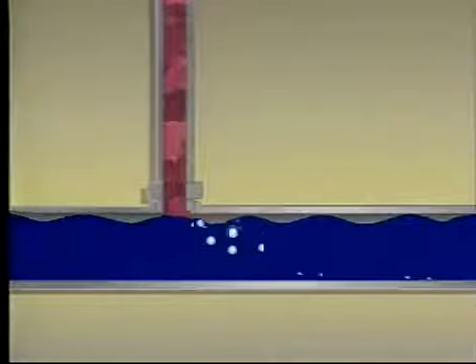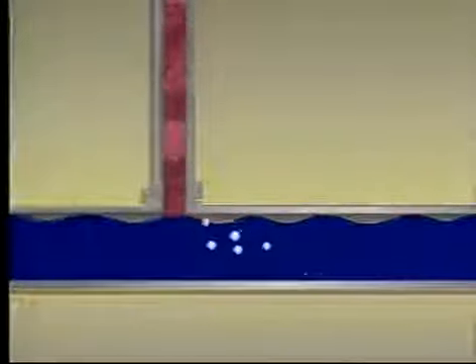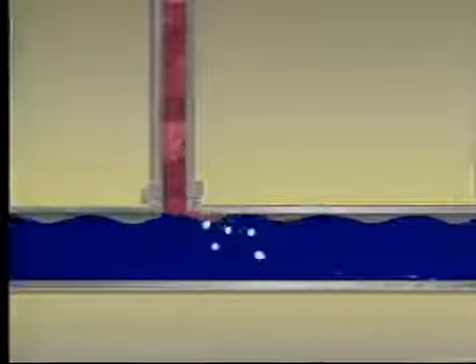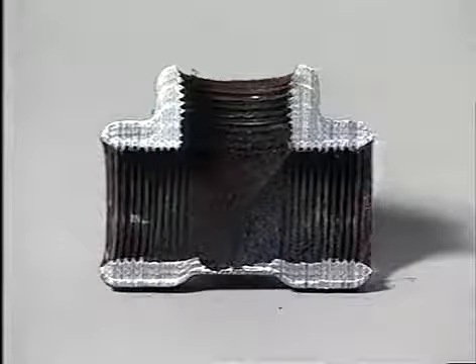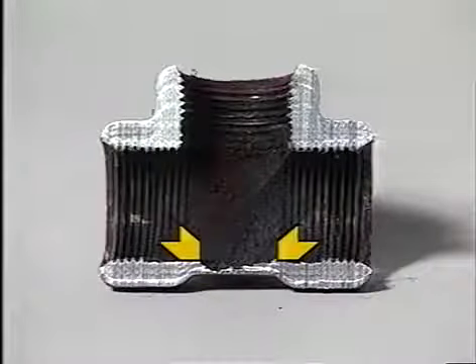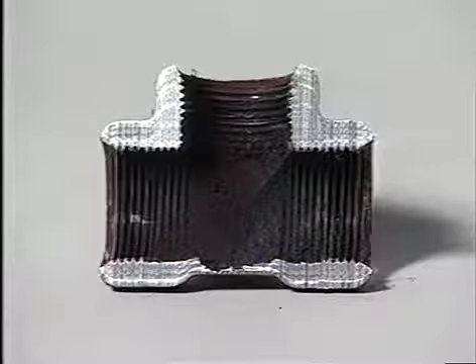The flash steam immediately collapses again when it encounters the relatively cool pump discharge water. This thermal shock often causes damaging water hammer. The localized sudden reduction in pressure near the wall chips away piping and tube interiors. Oxide layers that otherwise would resist further corrosion are removed, resulting in accelerated deterioration of piping and equipment.